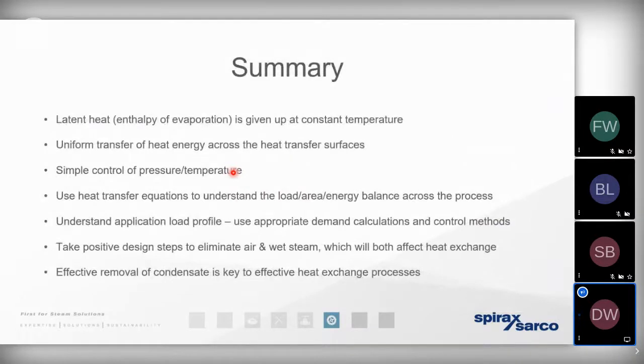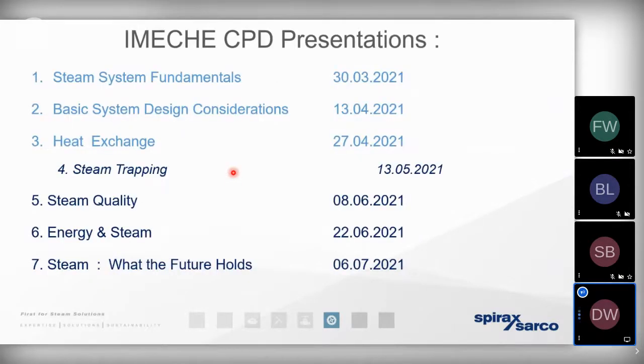It's the latent heat energy. It's the enthalpy of evaporation. That's the important number whenever we determine how we should be correctly sizing a heat exchanger. We know that steam gives up its heat energy by condensing. We know that the condensate doesn't have any value to the heat exchanger and therefore needs to be removed. And as with the previous presentation, we also know that keeping the steam as dry and free of air as possible is critically important. So in 2 weeks' time, we will continue with our journey, understanding steam trapping.